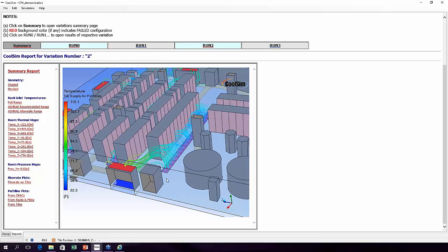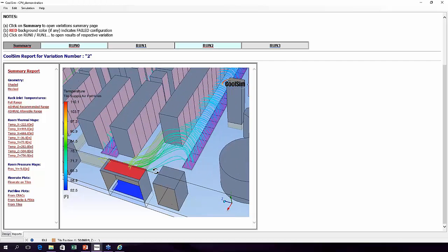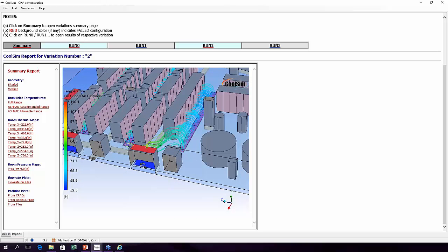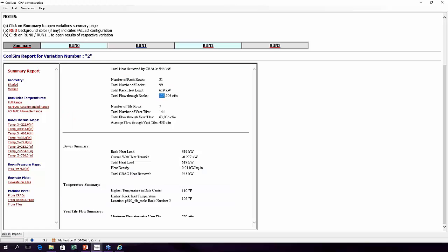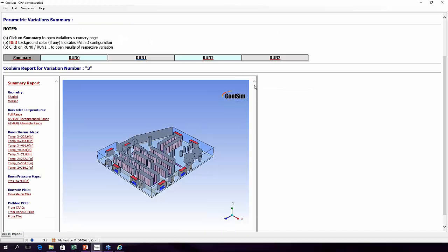The power consumed by a fan is a cube of the RPM, and you will also get more efficiency out of the cooling unit itself because its efficiency is proportionate to the delta T it sees across it, and the bigger the delta T, the more efficient the unit is. So that's a quick overview of what, and again, you export this and it all comes out the same way. You'd have 4 folders and 1 master, and it would assemble completely.